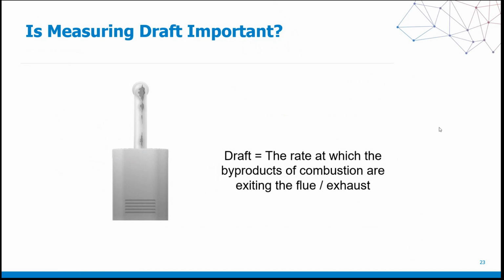Is measuring draft important? Absolutely it is. What is draft? Draft is a pressure measurement. It is the rate at which the byproducts of combustion are exiting the flue or the exhaust. And draft tells you a number of things. It tells you, first of all, how the combustion process is taking place and how properly it's being done, but it is also letting you know how the combustion byproducts are leaving the space. Because if the combustion byproducts are not exiting the flue or not exiting the space properly and being terminated outside, then you have byproducts of combustion that could potentially leach into a space, cause hazardous conditions, and obviously create issues with the appliance, which I'm going to go over.